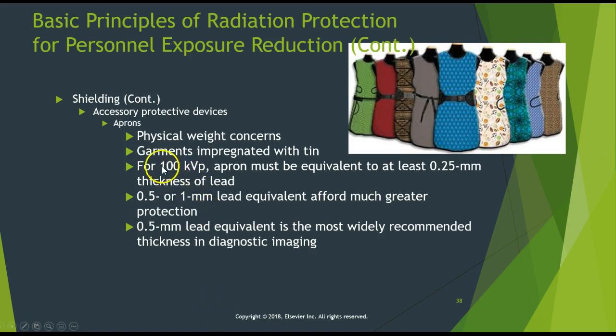For 100 kVp beam intensity, the apron must be equivalent to at least 0.25 millimeter thickness of lead. Actually, this is what is required. Okay, 0.25 millimeter thickness of lead is required for routine procedures. 0.5 or 1 millimeter lead equivalent affords greater protection, so that is what is recommended. So 0.5 millimeter lead equivalent is the most widely recommended thickness in regular diagnostic imaging.